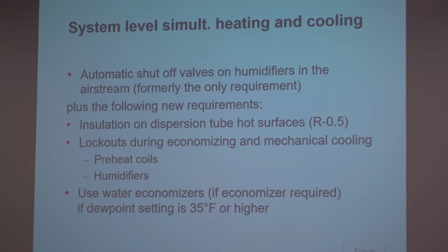And so this last bullet is what affects you, the one with the high dew point discharge requirement, which is you're not allowed to use an airside economizer if your space has to be humidified to above 35 degree dew point. If that's the case, then you would have to use a water economizer rather than an air economizer. You don't get out of it entirely, you just aren't forced to use one, not like you were anyway, but you're not allowed to use an air economizer, because we know that would increase your humidification load if you were doing active humidification.